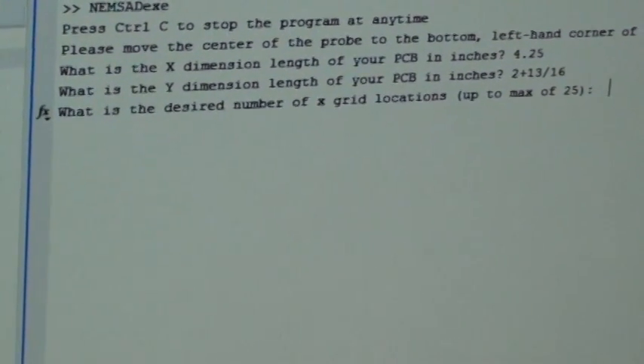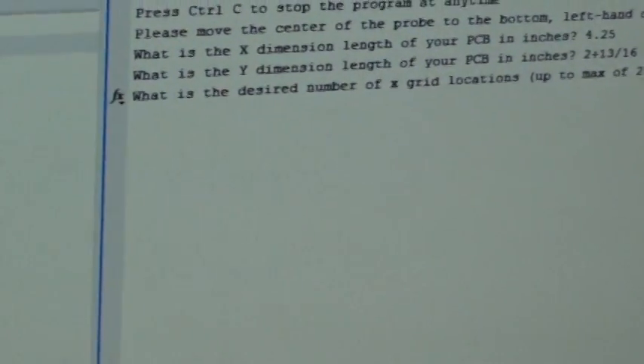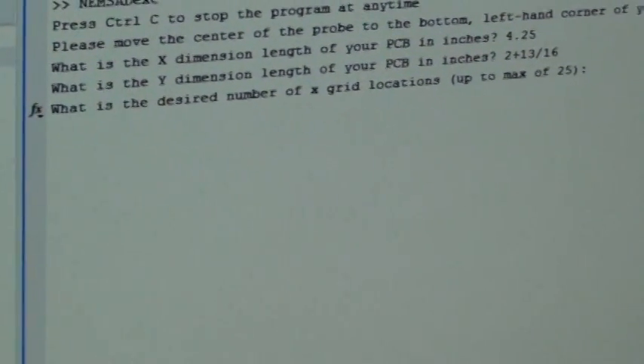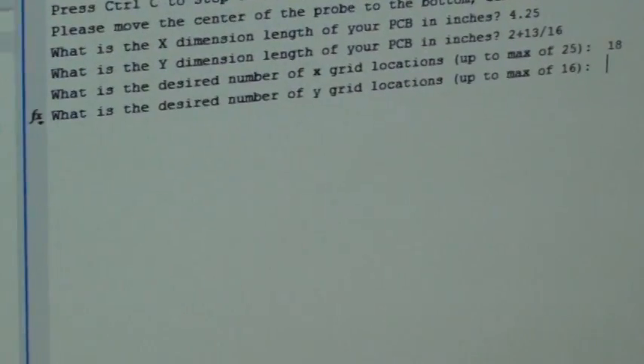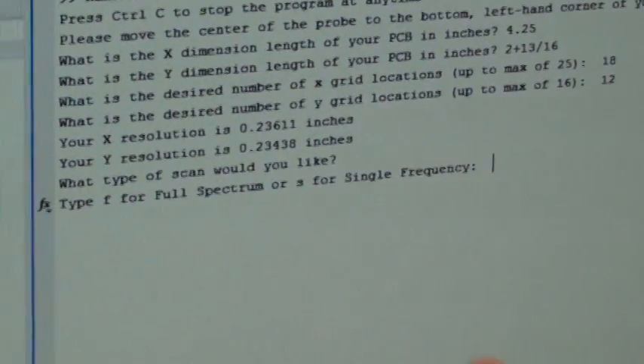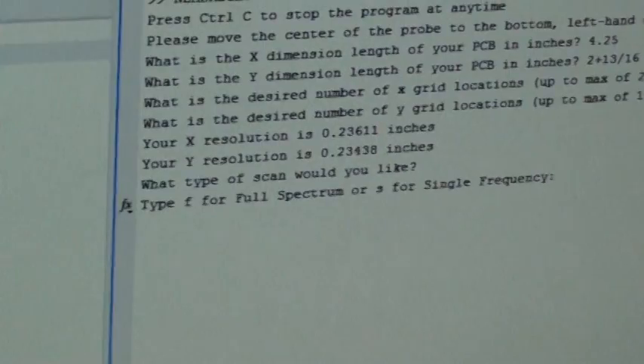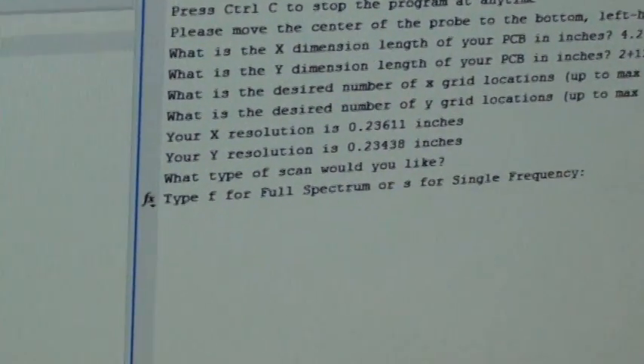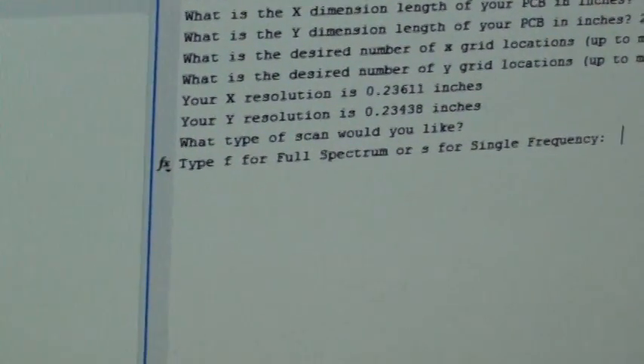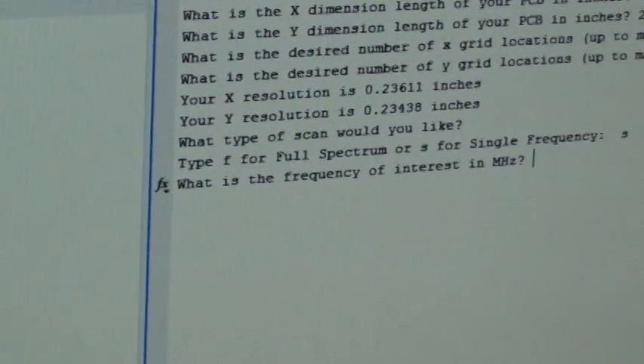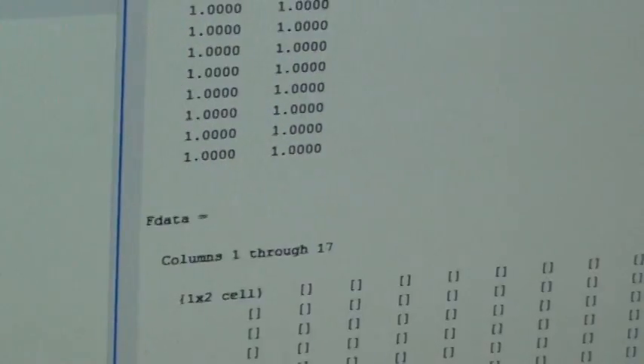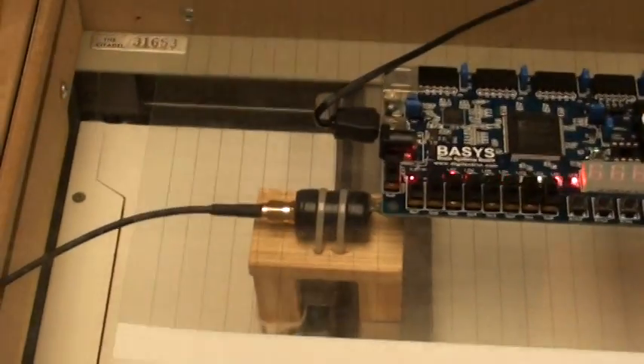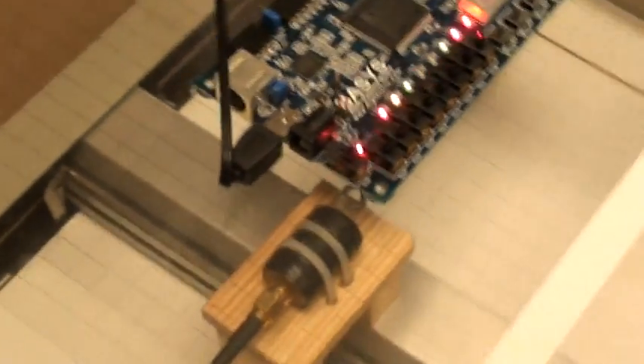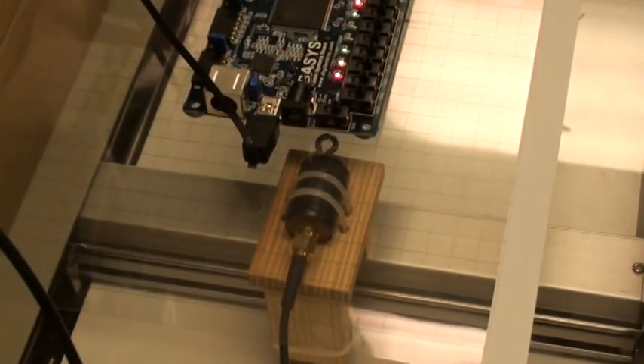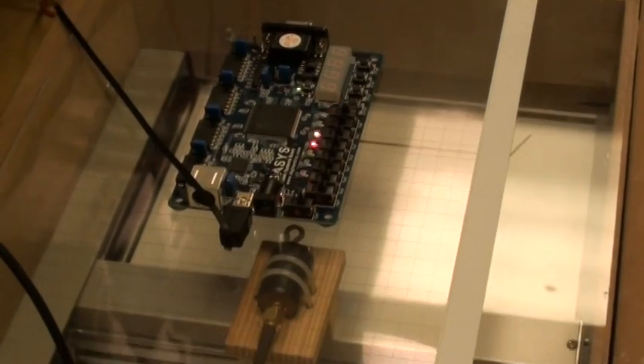So here you can see I can pick up to 25 cells as a result of the dimensions of my board. Let's go with 18 in the X and 12 in the Y. This gives me a corresponding resolution in inches that I'll use to go from a color plot to the physical location on my board. We'll do a single frequency scan, 48.1 megahertz. So if you look at the board, you can see about every 4 seconds or so the probe updates, moving up a column, goes one column at a time until the entire board is scanned.